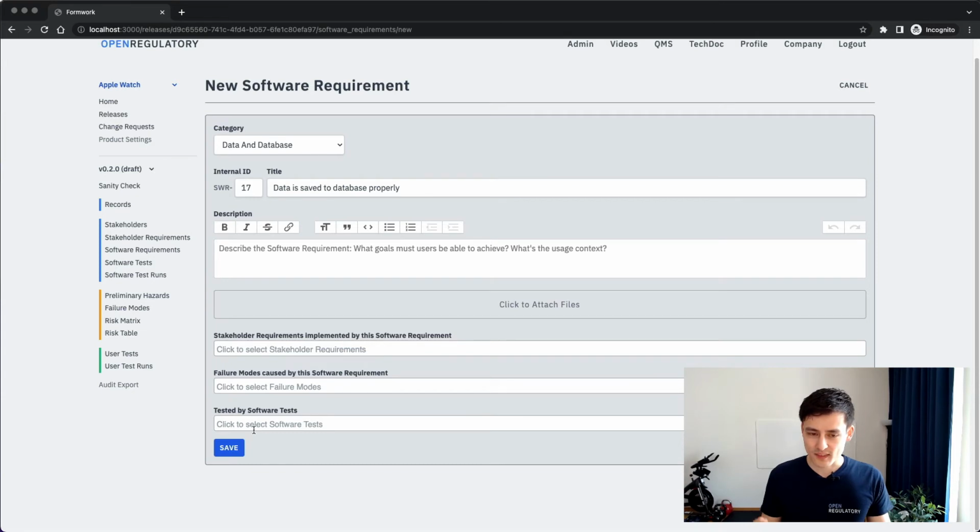And I won't go into all of these, but the most relevant part is, for example, each software requirement needs to be covered by at least one software test. And you have this whole end-to-end relationship going on, right? Because one software requirement could be covered by multiple tests, but one test could also cover multiple software requirements. So if you do this in a spreadsheet, this tends to be a gigantic catastrophe, and I've seen it at lots of customers already, which is very, very sad.